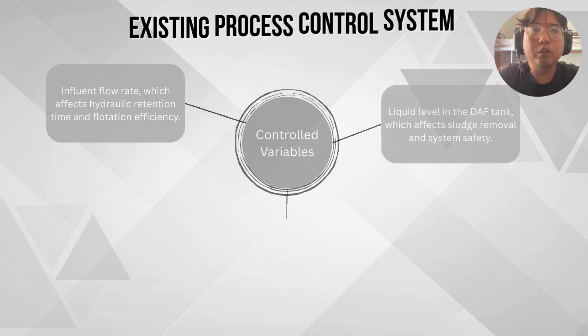The first process variable that we're going through is the control variable. Control variables are the key parameters that need to be maintained within acceptable limits to ensure effectiveness of the treatment. These include influent flow rate, recycle line pressure, wastewater pH, effluent turbidity, suspended solids concentration, and also liquid level in the DAF tank for this process. Although these variables are monitored using flow meters, pressure gauges, and also the sampling points, they are not automatically controlled.